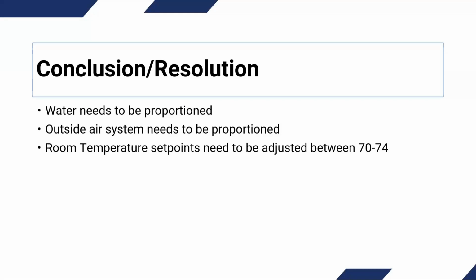The other thing that we see is people will drop the temperature set points, hoping that, well, a colder building, units will run longer, therefore dehumidify better. That's never the case. We always tell the owners the way relative humidity works is it's relative. A 65% relative humidity building at 68 degrees is going to drop down to 60 or so if you raise the temperature up to 70. That doesn't mean that it's comfortable, but again, relative humidity is relative, and that's why we look at grains of moisture when we're dealing with humidity control.